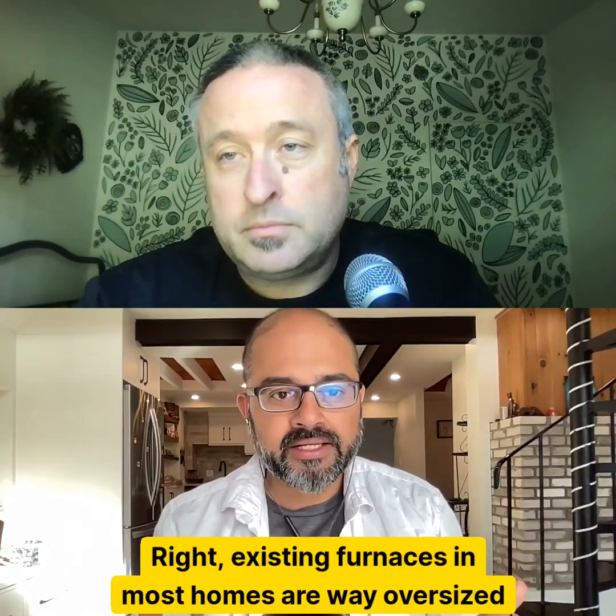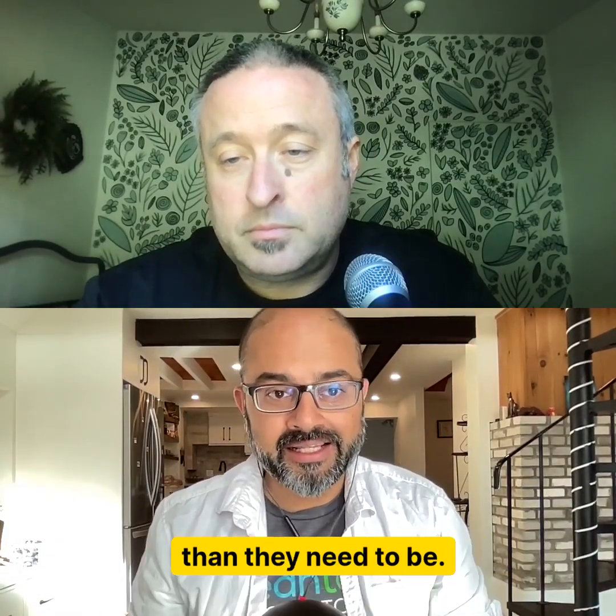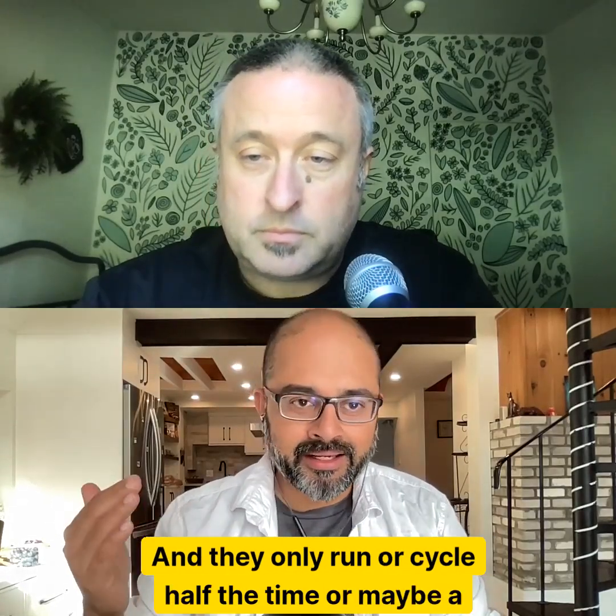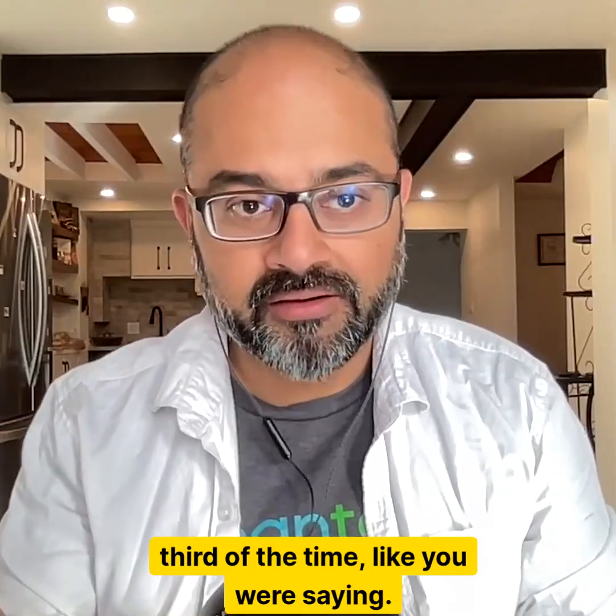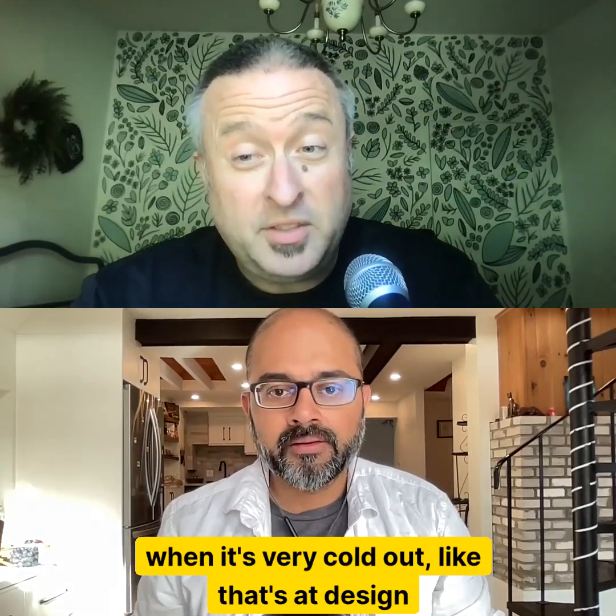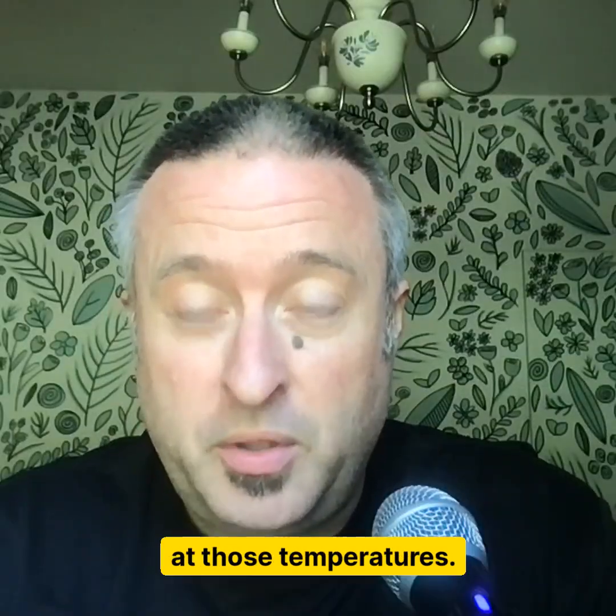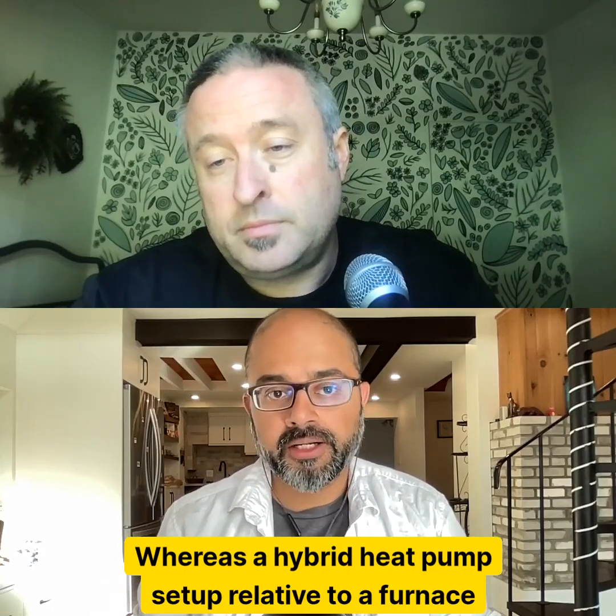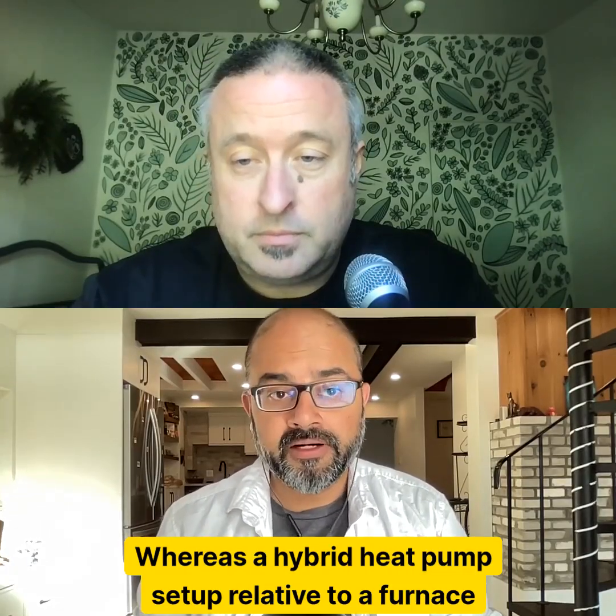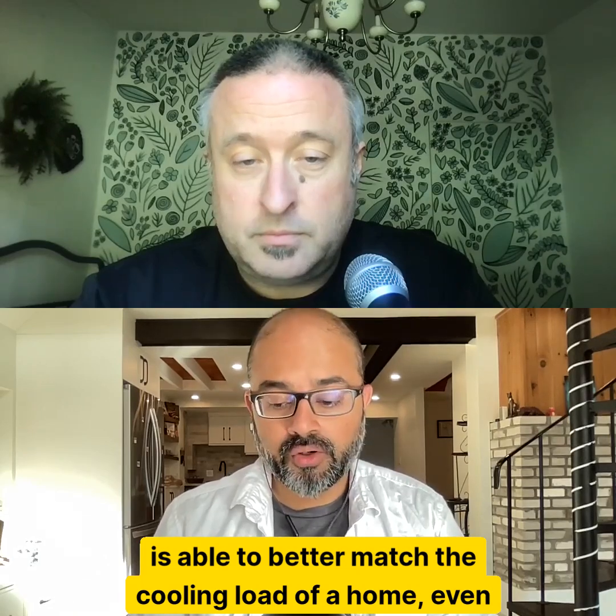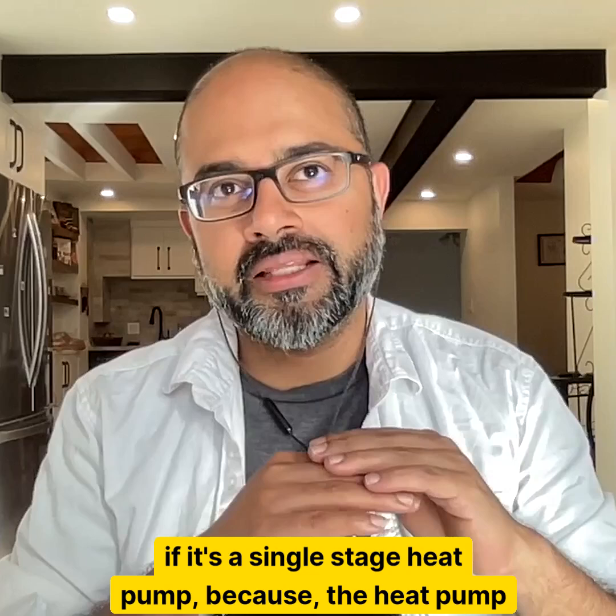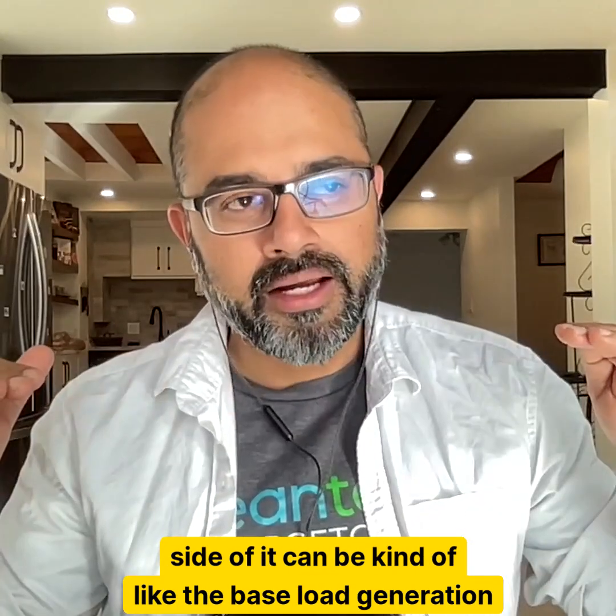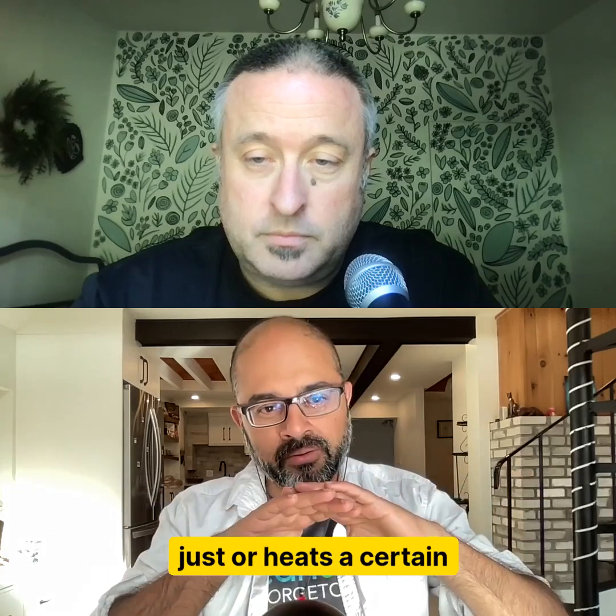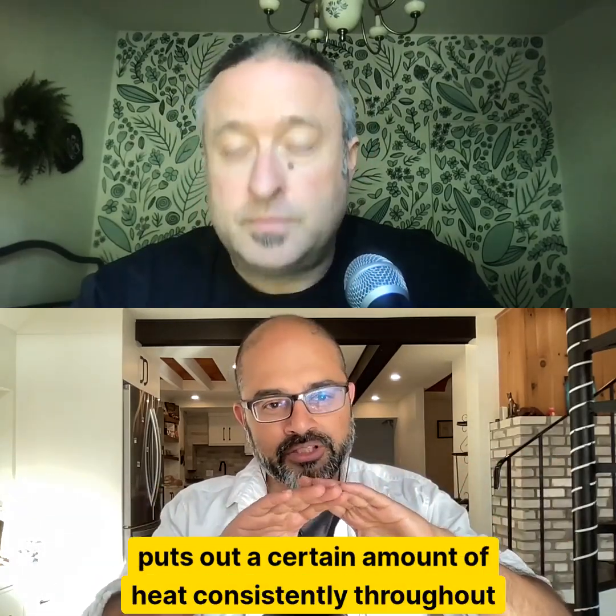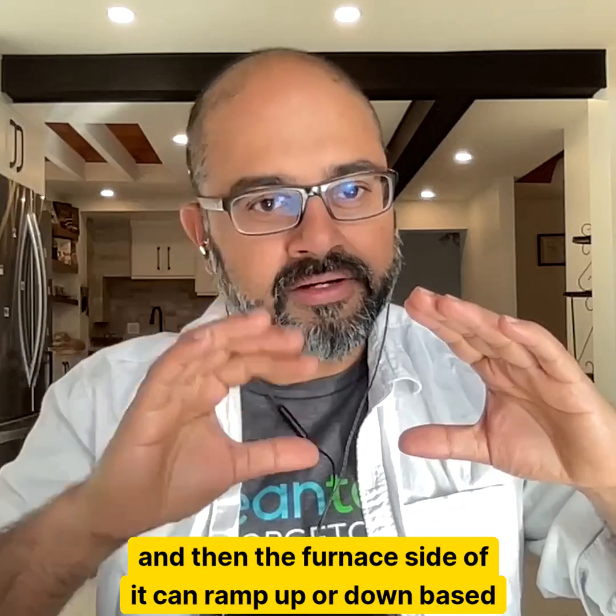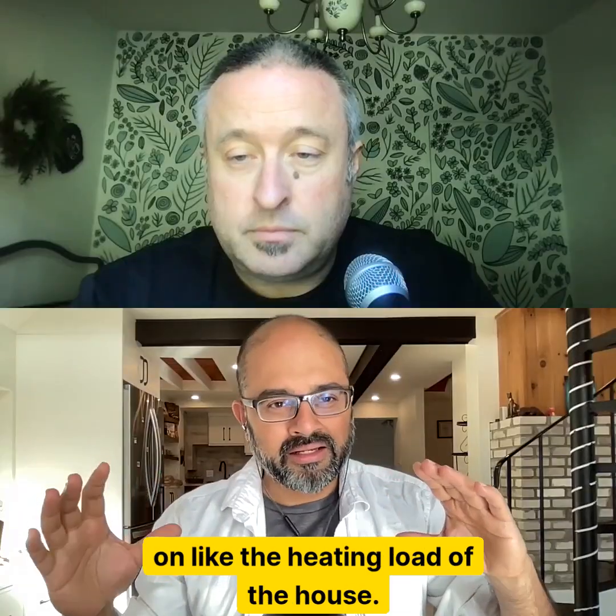Yeah. Right. Existing furnaces in most homes are way oversized than they need to be, and they don't run nearly all the time, and they only cycle half the time or maybe a third of the time, like you were saying. When it's very cold out, that's at design temperatures, where we only spend a few hours a year at those temperatures. Whereas a hybrid heat pump setup, relative to a furnace, is able to better match the load of a home, even if it's a single stage heat pump, because the heat pump side of it can be kind of like base load generation, or puts out a certain amount of heat consistently throughout, and then the furnace side of it can ramp up or down based on the heating load of the house.